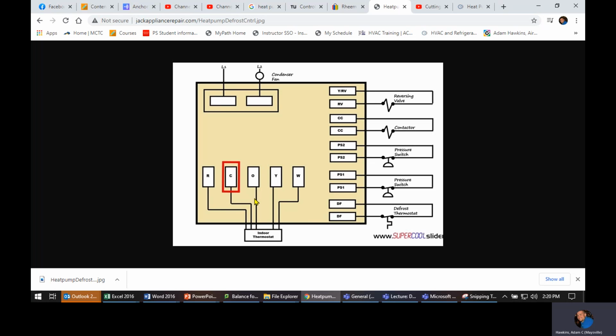Well, the stat is sending 24 volts from red inside to orange outside, going through the air handler, but it's just bypassing the air handler and going straight to the outside unit, and that's going to be on all the time. So it's always going to be in that position, because as soon as you switch that stat to cooling, that's going to energize or de-energize that reversing valve depending on its position. Then when it goes to kick on, it's going to just bring it on in the right mode. Now, this O or B can switch when it comes to defrost, but for normal operation, it's just going to stay put whichever way it's in. And then when you turn the thermostat off, it's going to go into its normal position. So it's going to be energized or de-energized, cooling or heating.